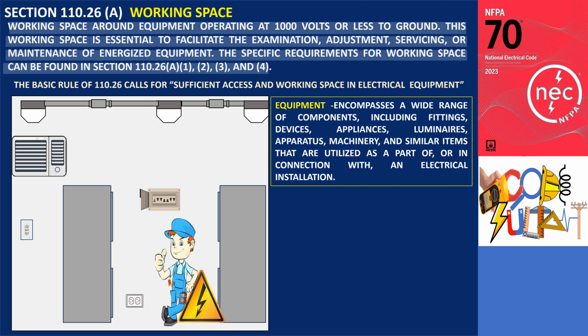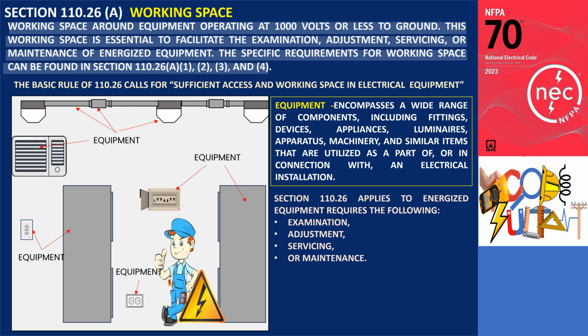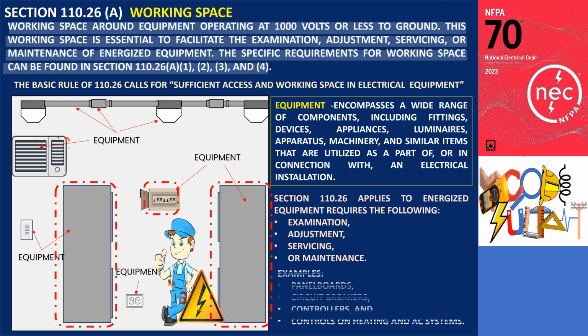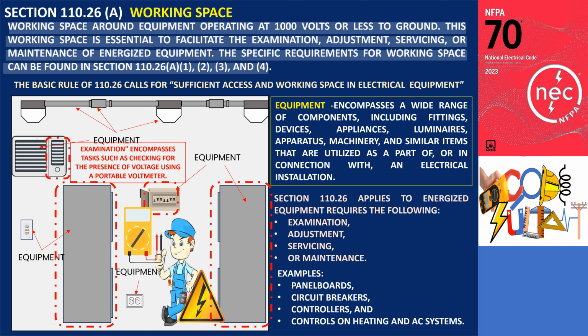However, the definition of equipment in the NEC encompasses a wide range of components, including fittings, devices, appliances, luminaires, apparatus, machinery, and similar items that are utilized as a part of, or in connection with, an electrical installation. If any of this equipment requires examination, adjustment, servicing, or maintenance while energized, the provisions of Section 110.26 apply. Examples of such equipment include panelboards, circuit breakers, controllers, and controls on heating and air conditioning systems. It is crucial to note that the term examination encompasses tasks such as checking for the presence of voltage using a portable voltmeter.